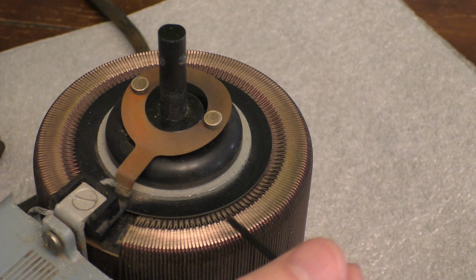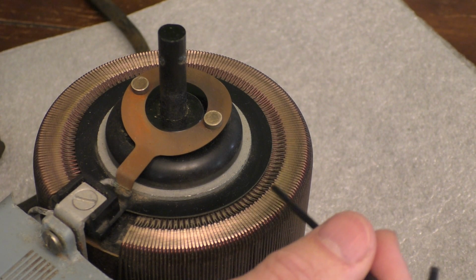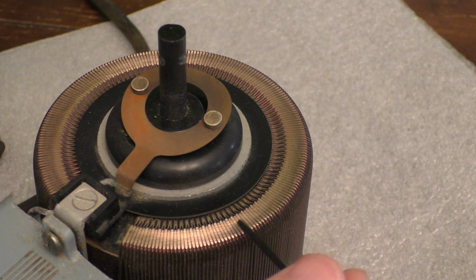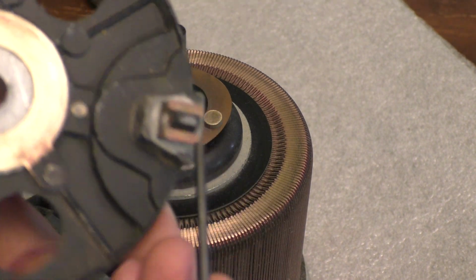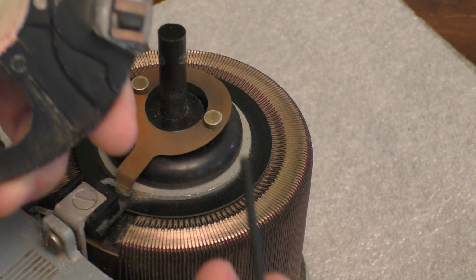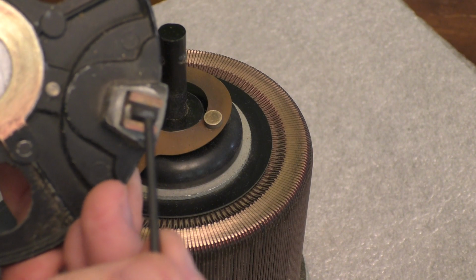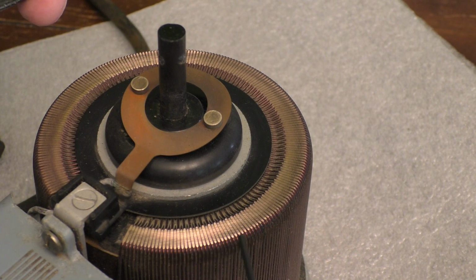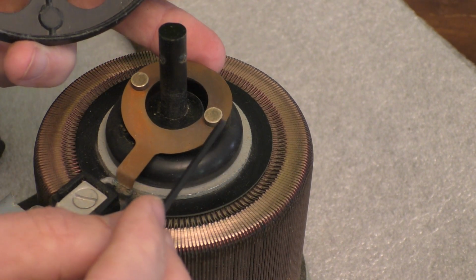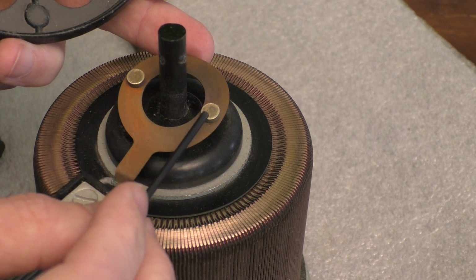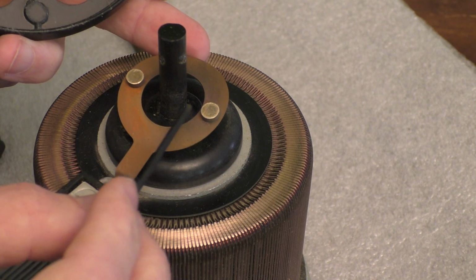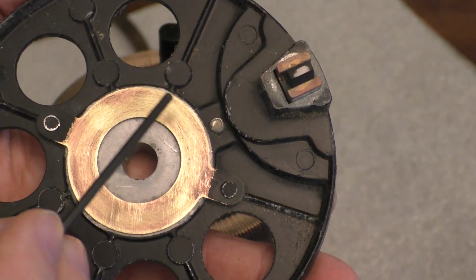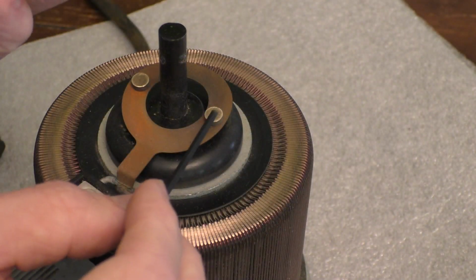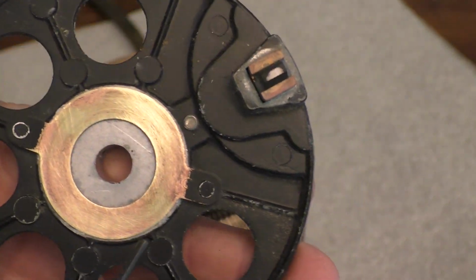So I had to use a little sandpaper and just sanded off all that black to expose these nice shiny copper wires. That black carbon was basically preventing the bushing from being in contact with the wires. I also sanded these contacts a little, which are still a bit dark in the middle, and sanded this ring too, which was very blackened and had poor contact with these rings. That's basically all I did.